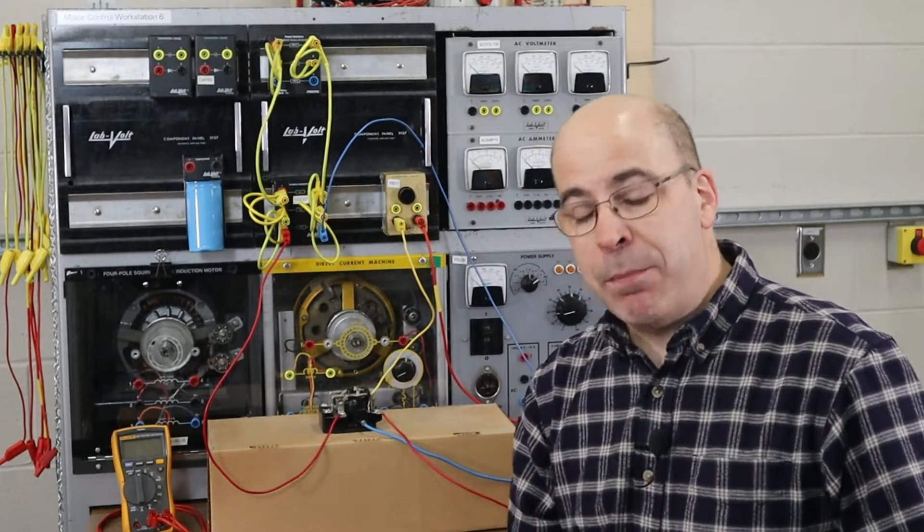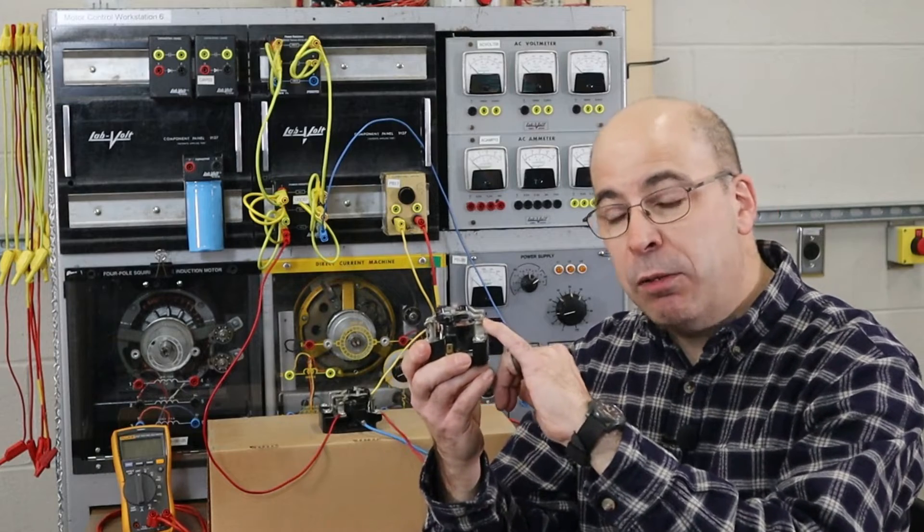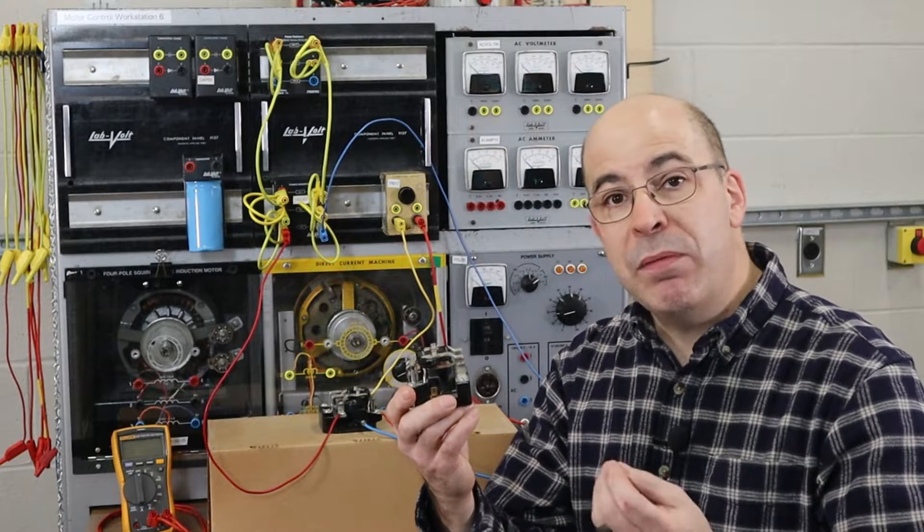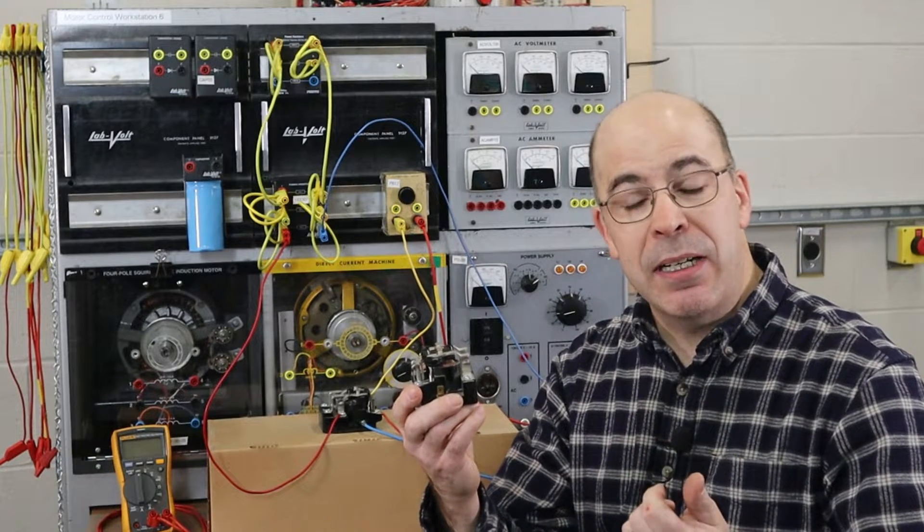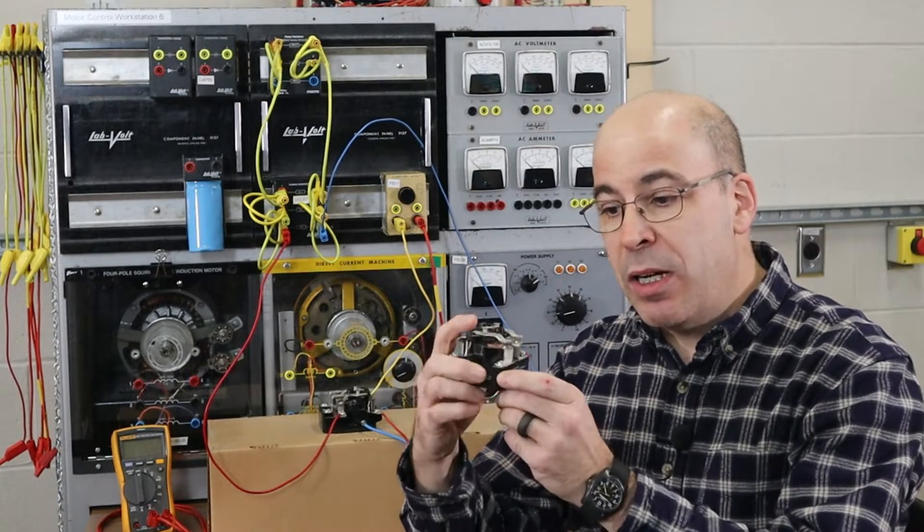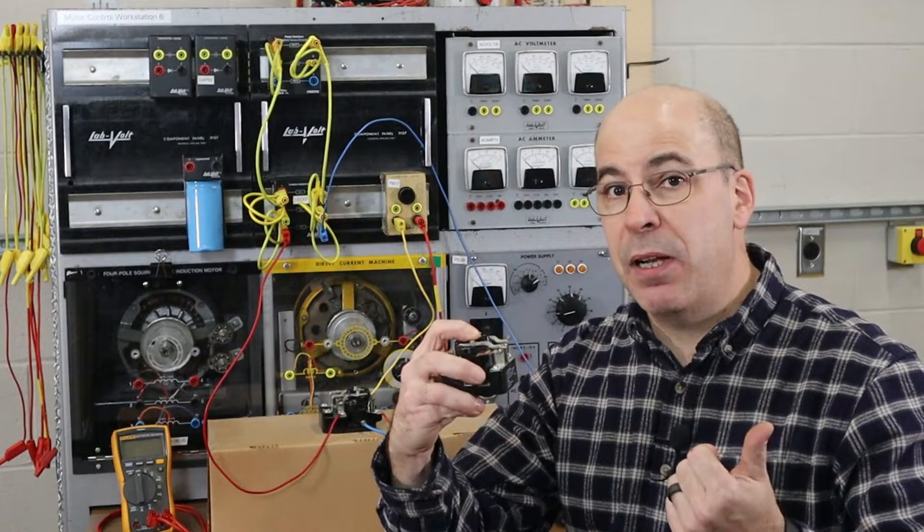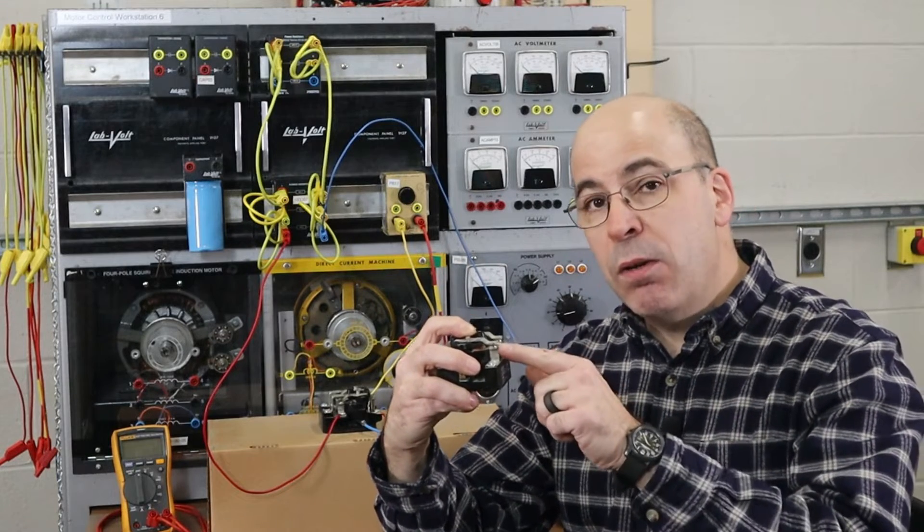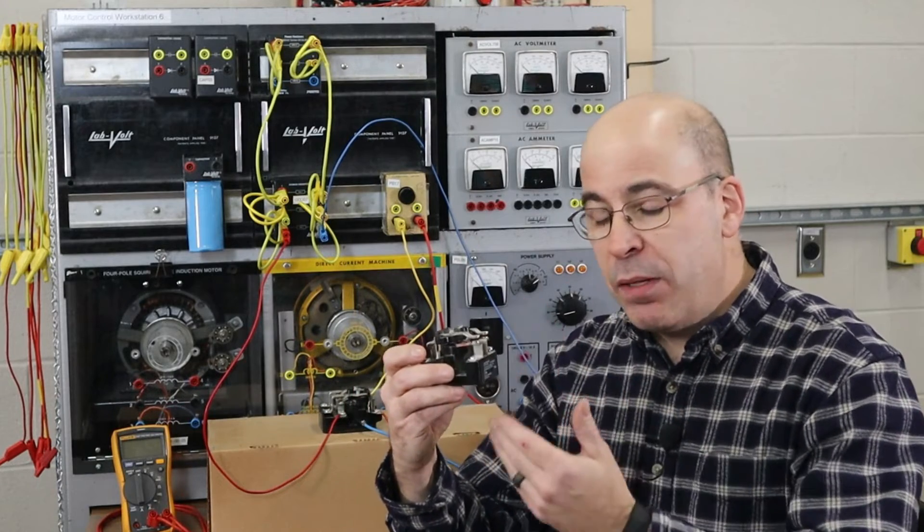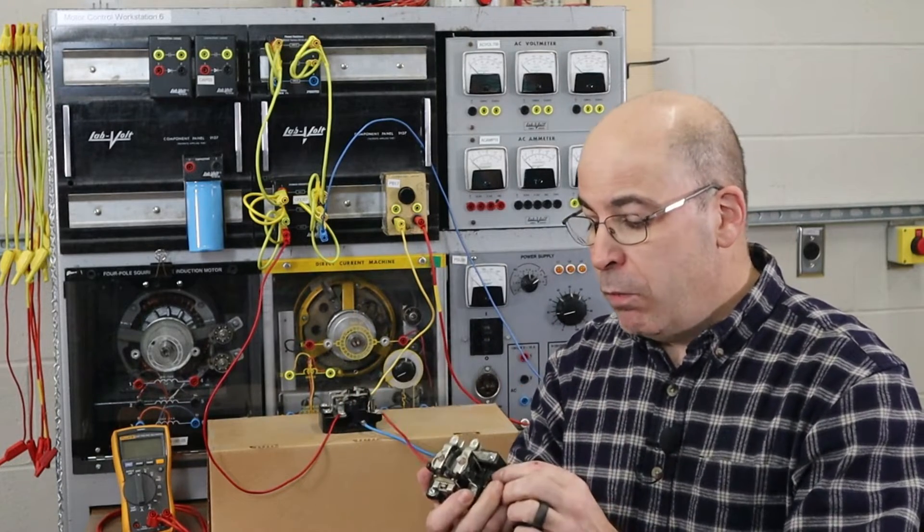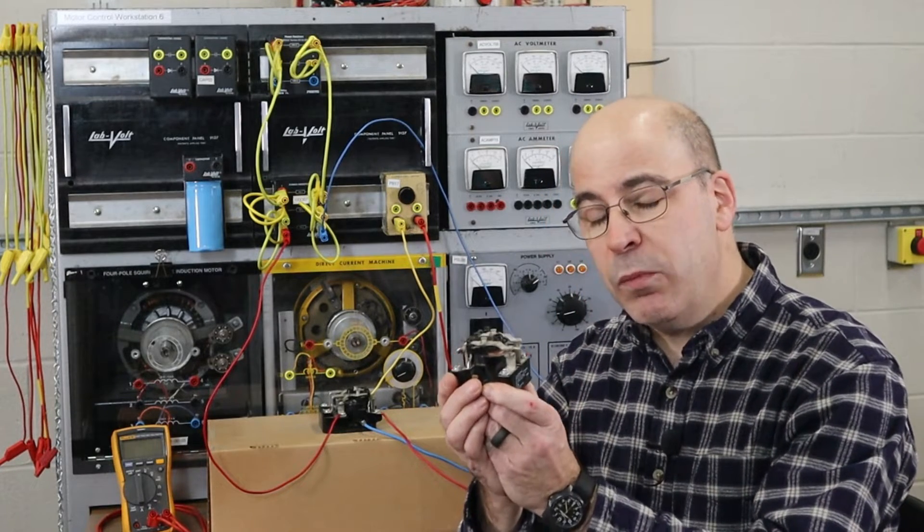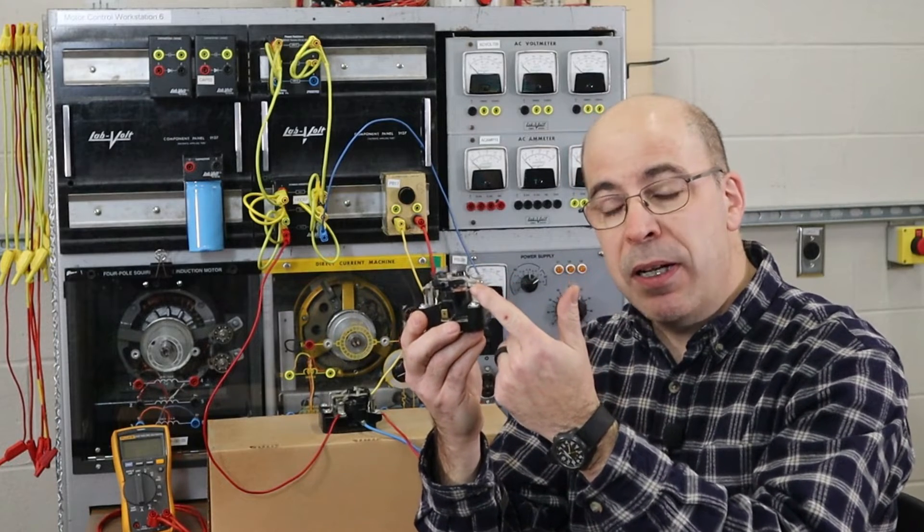Left unchecked, the contact material is going to get pitted. When we have pronounced arcing, we're also going to see a lot of heat. Left unchecked, the contacts can actually either burn themselves out or weld themselves together. For the longevity of the device, it's not ideal. What can we do to solve this problem? One way we can do this - right now we only have the one contact. But if we switch the type of device, meaning if I went to a contactor...